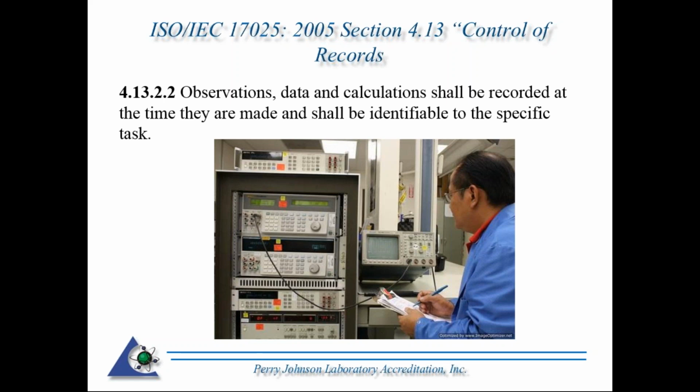4.13.2.2. Observations, data, and calculations shall be recorded at the time they are made and shall be identifiable to specific tasks. In other words, when you're collecting data for your testing calibration, it should be done in real time. Makes sense. It's not something you want to forget.